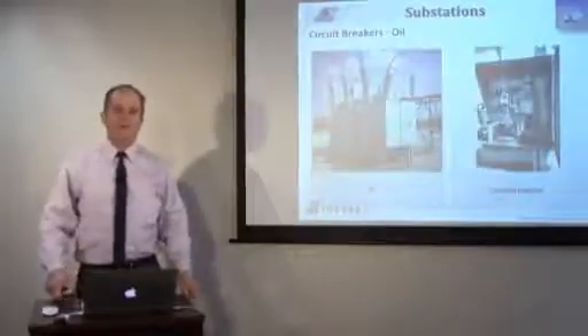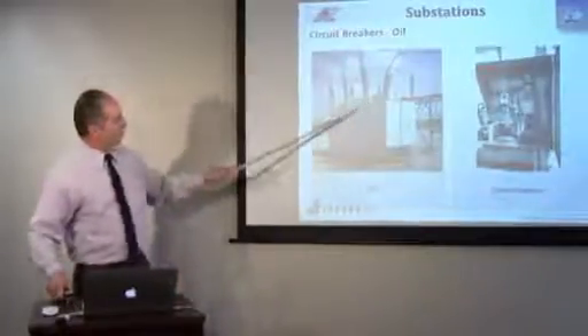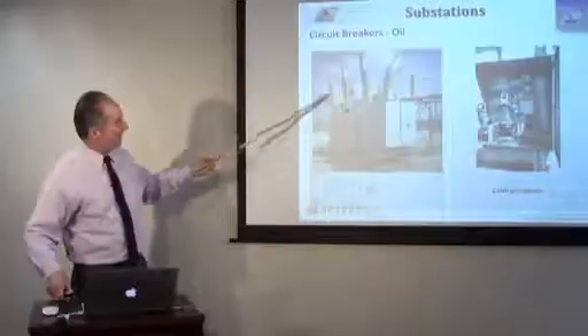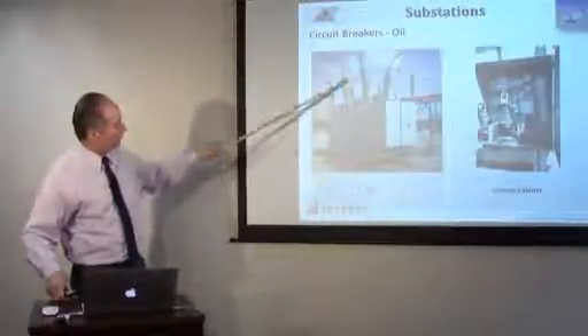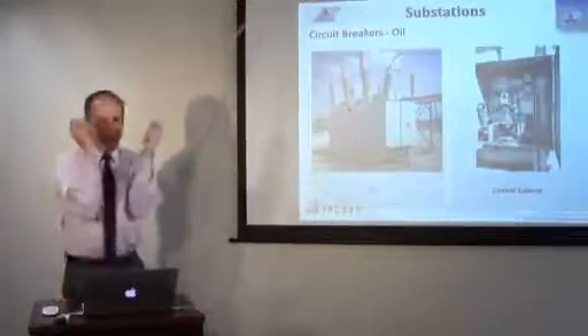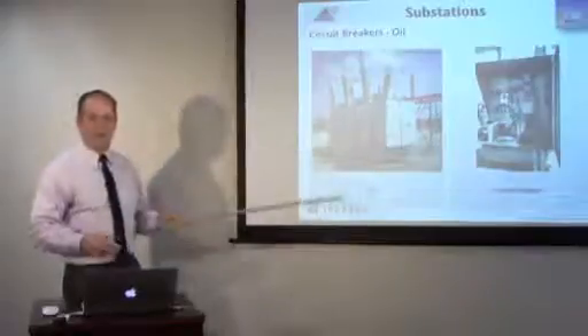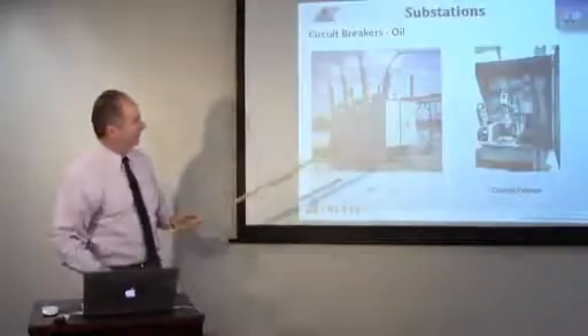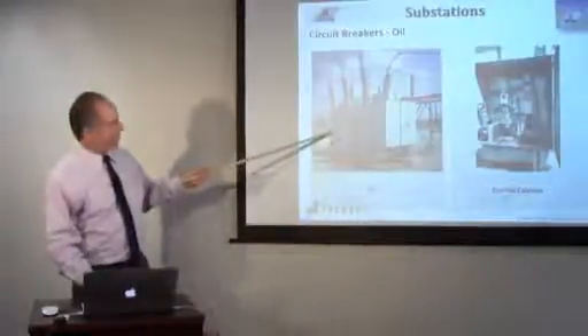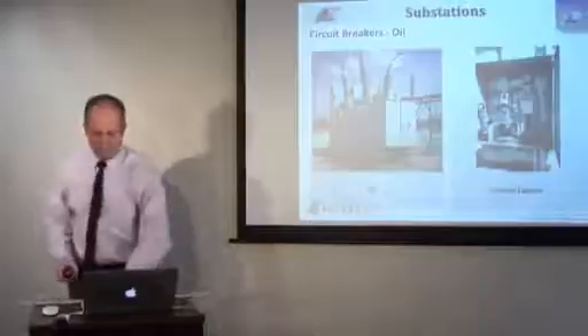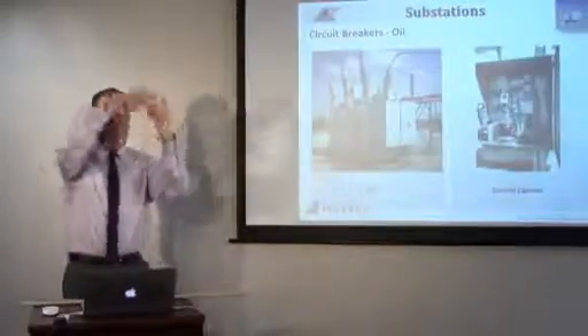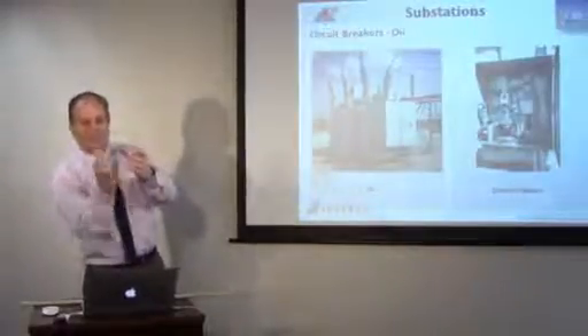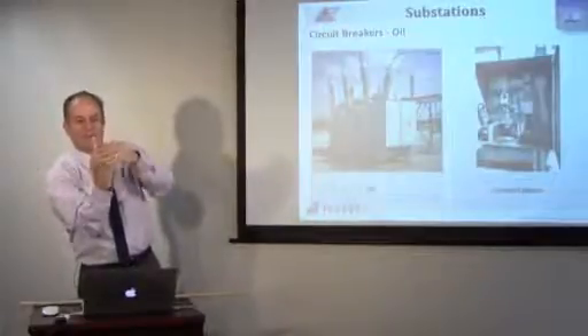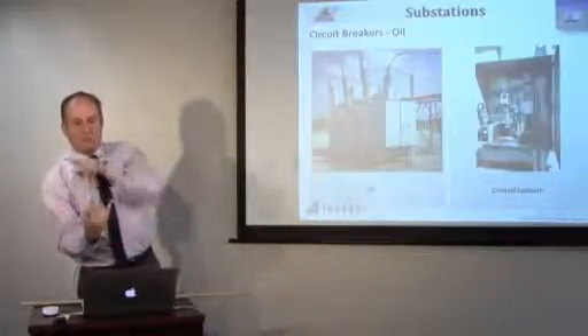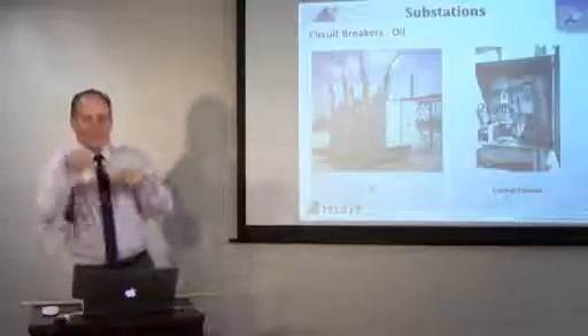Okay, here's an oil circuit breaker. It's filled with oil. What happens is you've got a bushing that goes down here and a bushing from the other side. They're in a V because the dielectric strength in oil is better than air. In air, you have to keep them farther apart. In oil, you can keep them closer together. But down on the bottom, you have almost like a U shape. At the bottom of the bushings you have a U that goes up and makes a connection. If you push it down, it breaks the connection. If you pull it up, it makes the connection.